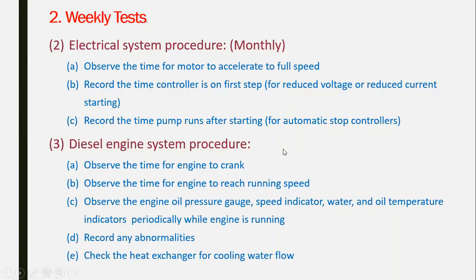And for the diesel pump, the procedure will be observing the time for the engine to crank, observing the time for the engine to reach the running speed, recording and observing the engine oil pressure, speed indicator, water, oil level, temperature, recording any abnormalities, and checking the heat exchanger for cooling water flow. So take all of these records for the weekly and the monthly test.